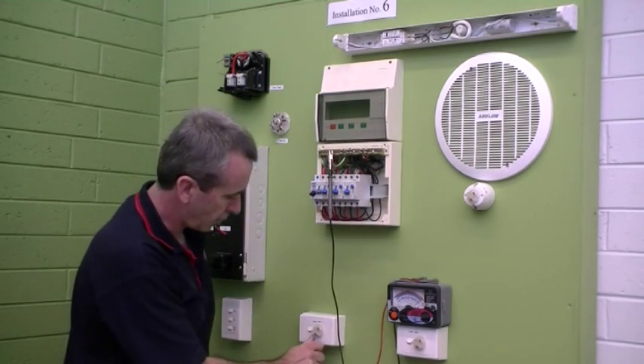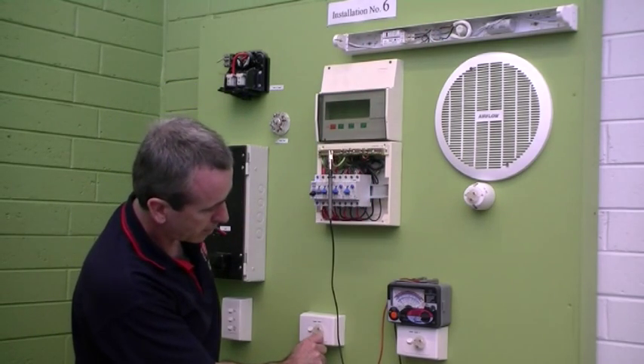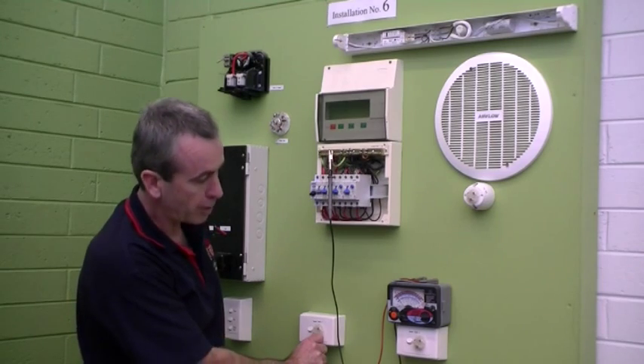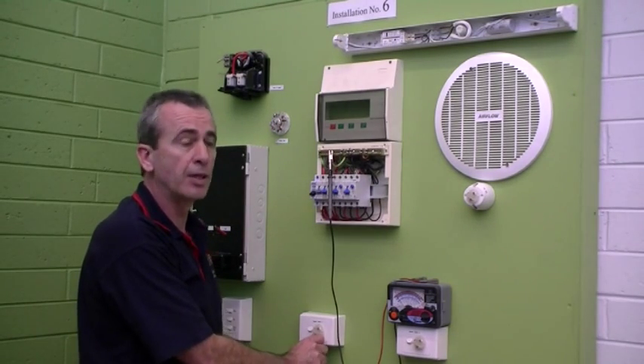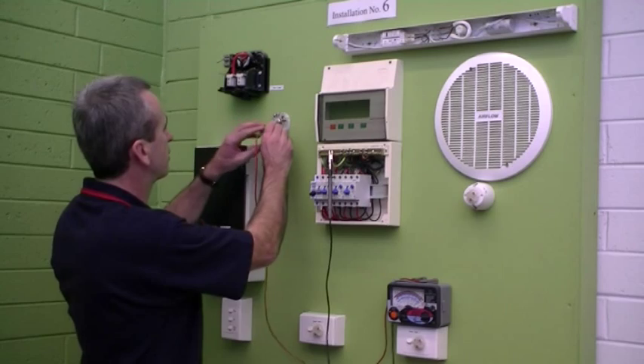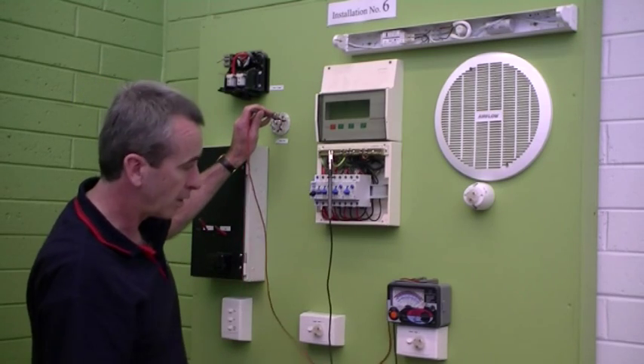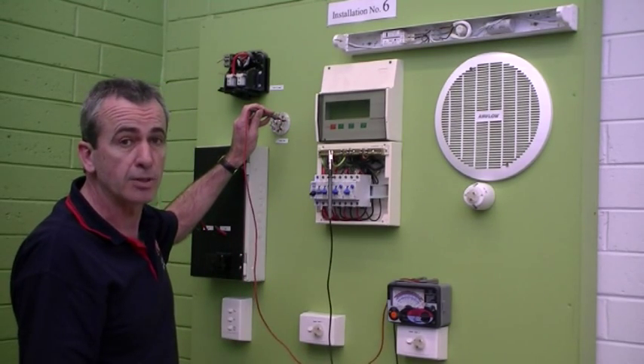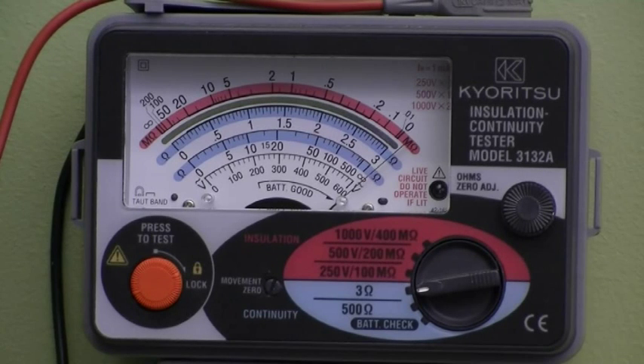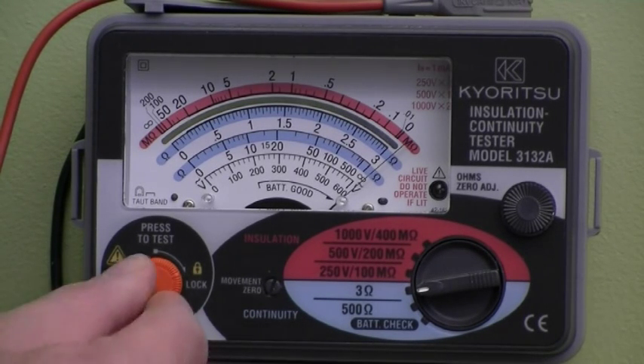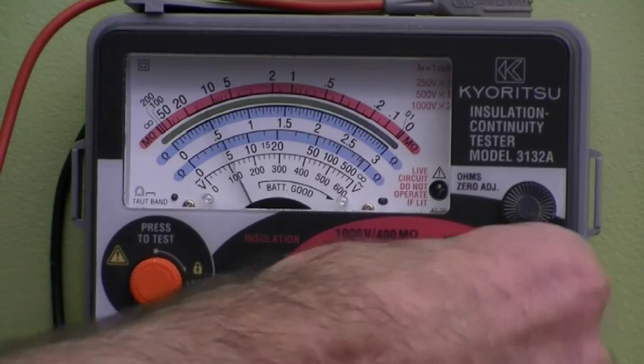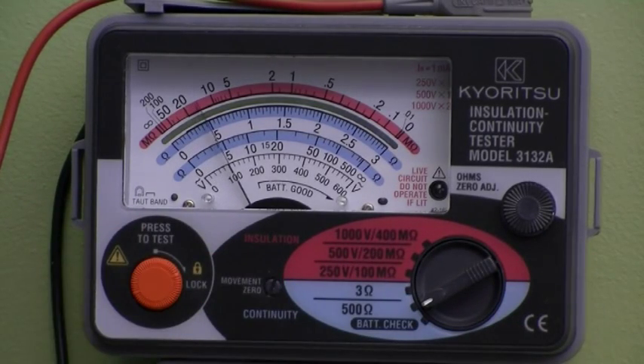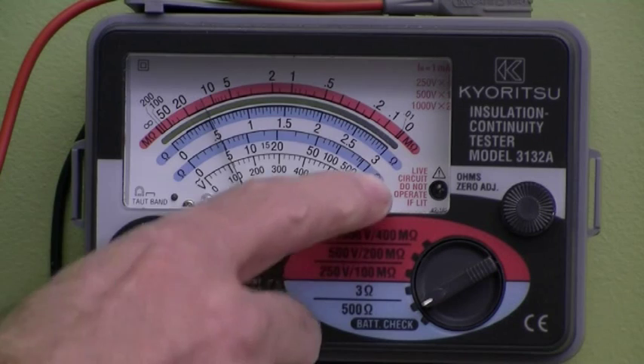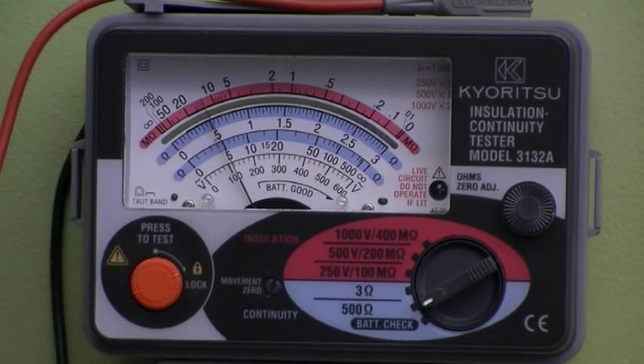The resistance of the socket outlet, once again, about 0.05 of an ohm, very low value. And at the ceiling rose, I've got a resistance there of greater than 3 ohms. The meter's indicating a value higher than 3 ohms, but I'll just change the range to see if it is an open circuit or a higher resistance. I'm on the 500 ohms range, and it actually is saying that there is 5 ohms of resistance there.